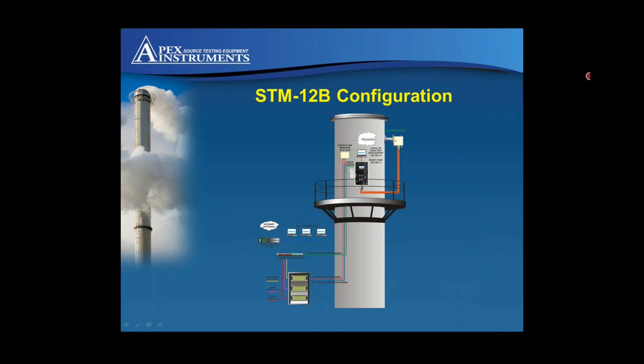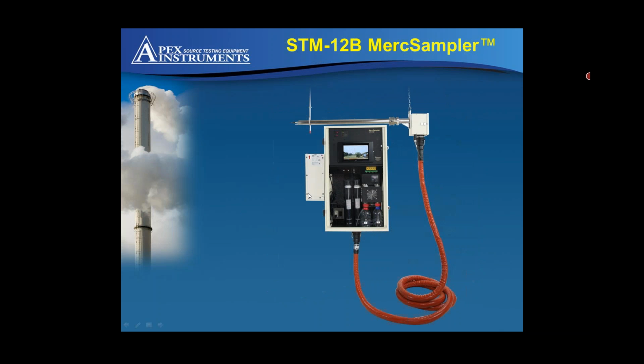You can see here, from a day-to-day running basis, we've got the AC unit built on the side, which will keep the enclosure. Heat exchangers, heat and cold. Right, it's heat and cold, so it'll keep it running in both summer and winter if we're exposed to the elements. Our Stirling cooler here, the reason we chose this design is how well it can run in ambient temperatures. We can go right down into the minuses or right up into the 140s with that Stirling engine itself. But again, that's housed within our NEMA enclosure with our HVAC unit attached to keep it at a constant temperature. And we've never had any issues with these. So the short time it's exposed to the elements when you're up there once a week changing traps will not affect the system at all. It'll go along like it's never been opened up. Okay.